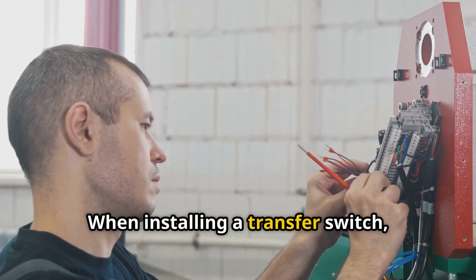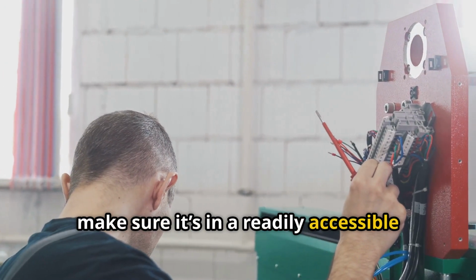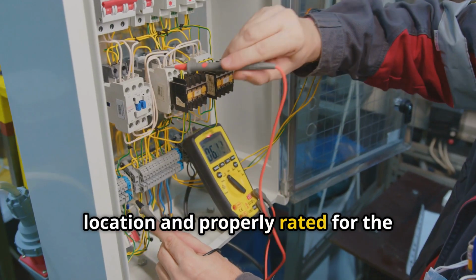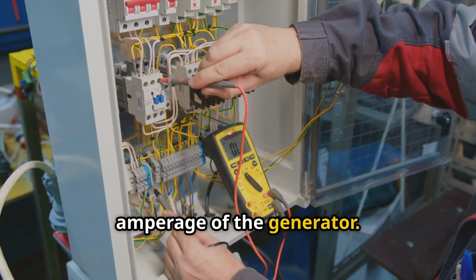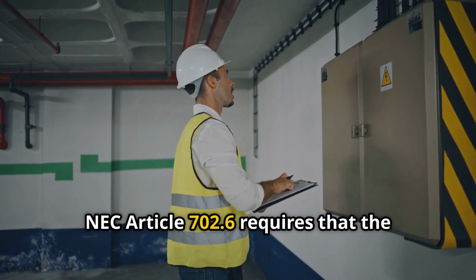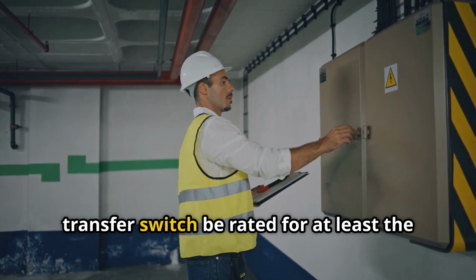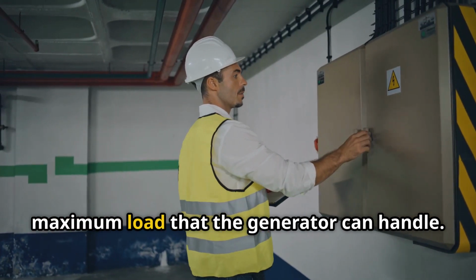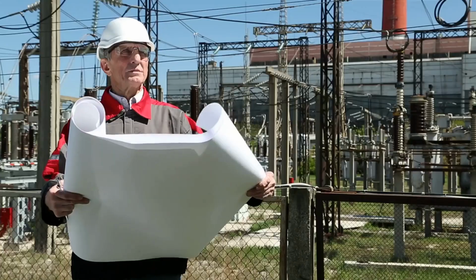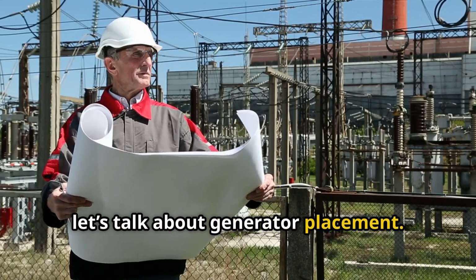When installing a transfer switch, make sure it's in a readily accessible location and properly rated for the amperage of the generator. NEC Article 702.6 requires that the transfer switch be rated for at least the maximum load that the generator can handle. Next, let's talk about generator placement.